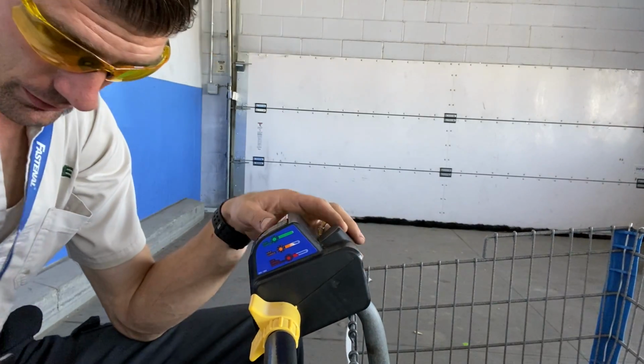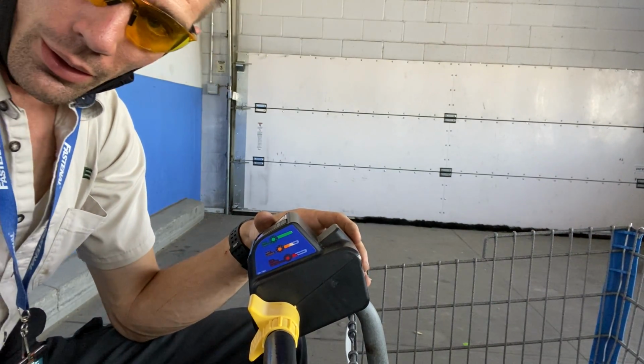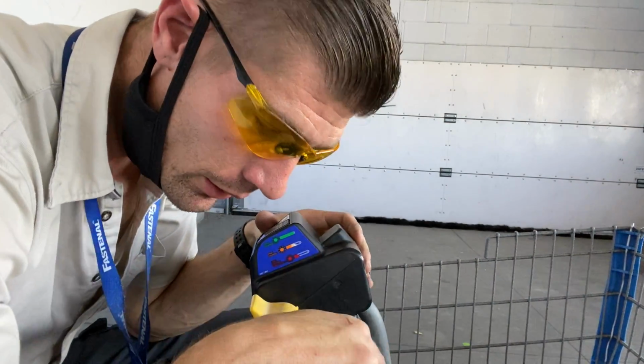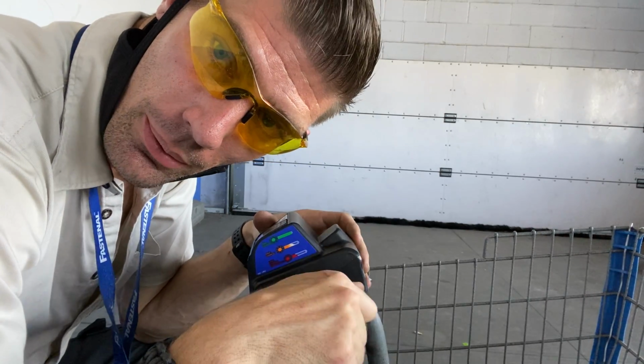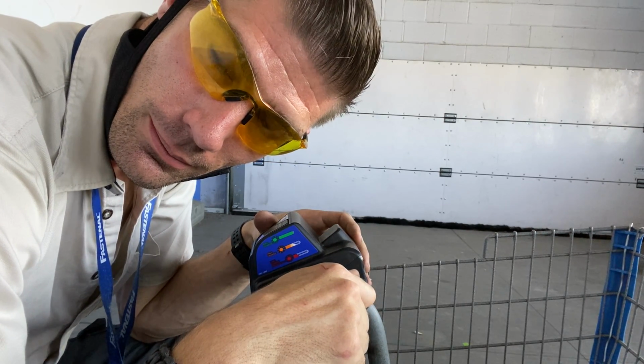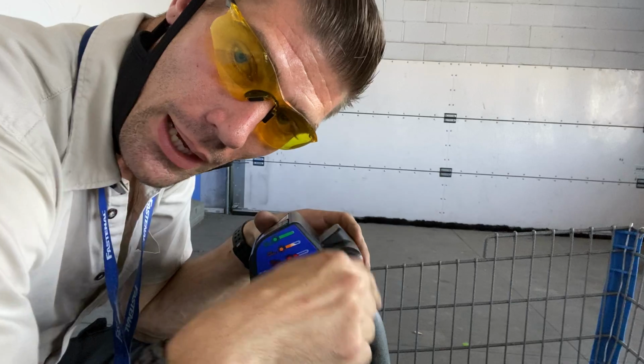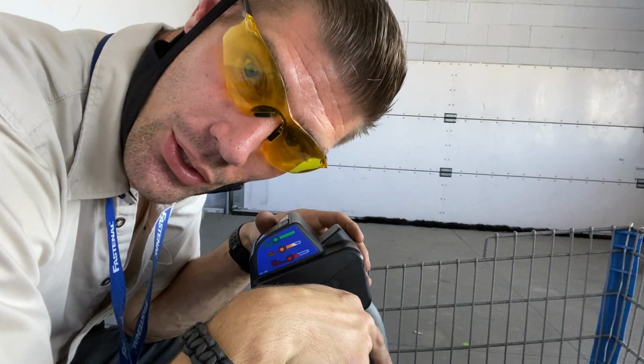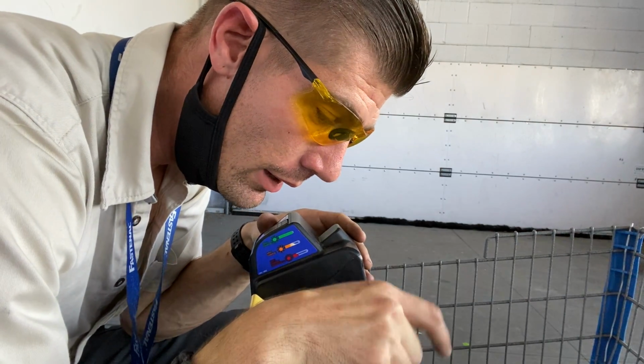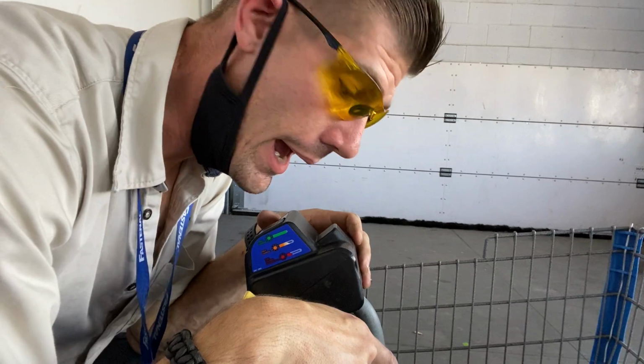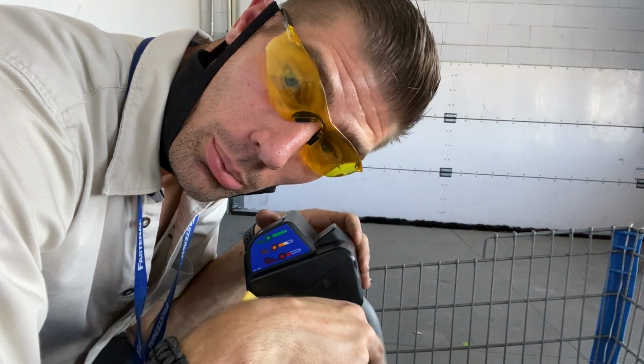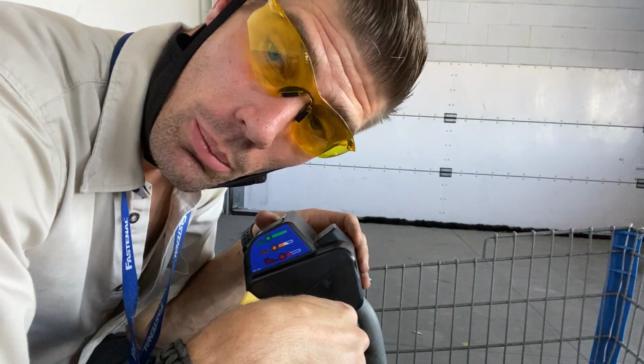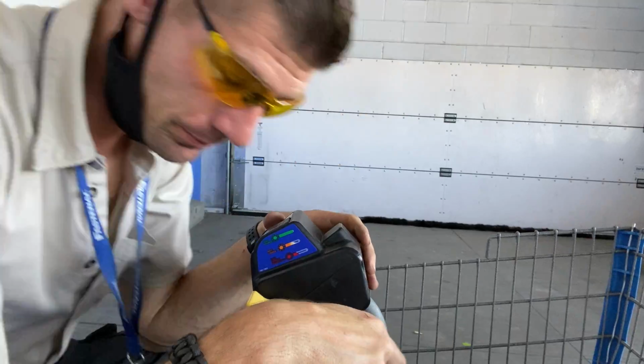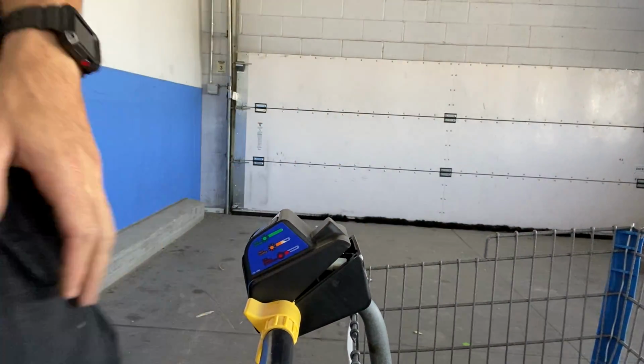So now we've got a problem here. You hear that clicking noise and the beep. That's the motor trying to engage and it's not working. I suspect we have a loose wire or a broken wire somewhere between the motor controller and the actual motor. So let's take a look at that.